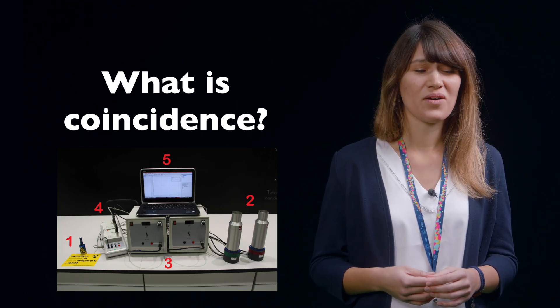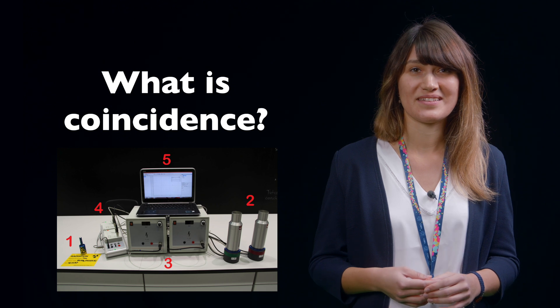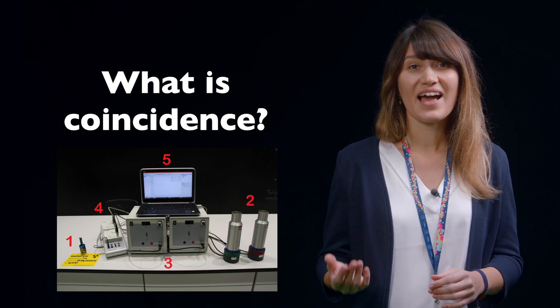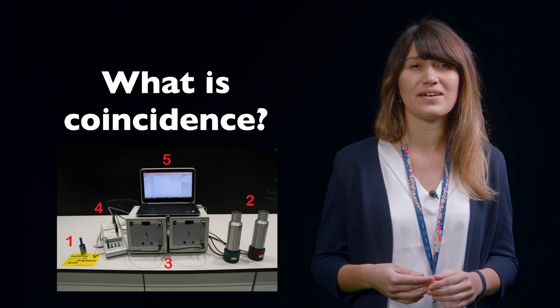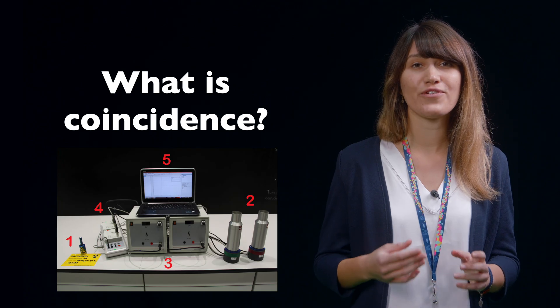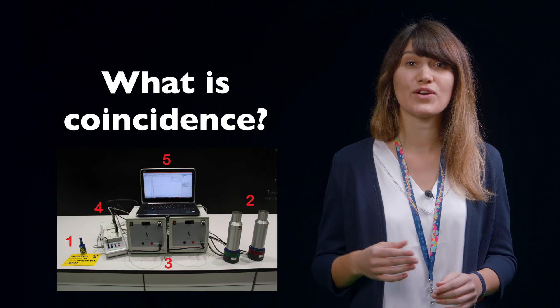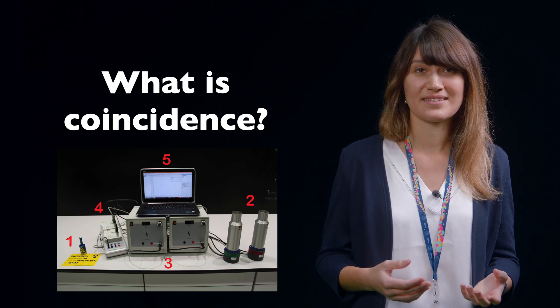Now, how precise is that measurement? In our case, at the same time means that there are maximum 4 microseconds between the first signal and the second signal.